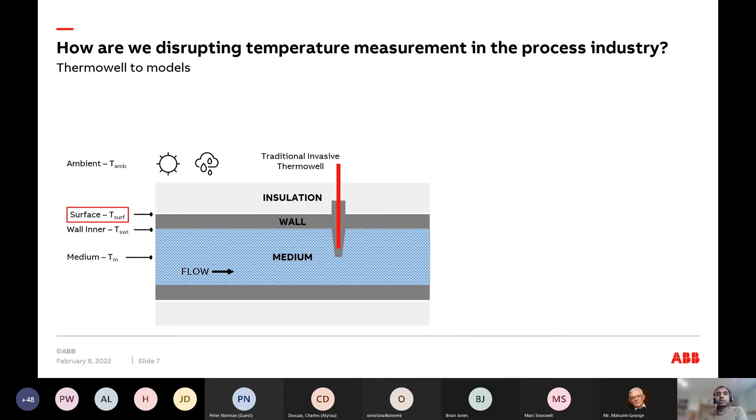Even in the most traditional measurements, there is a transfer error that can go undetected today and that we live with. Our approach is completely different. If you take away the thermowell and turn the pipe into the sensor, the only real measurement you have is the surface temperature of the pipe. Theoretically, how good can it be? And assuming you can measure the surface temperature accurately, can you predict the medium temperature?